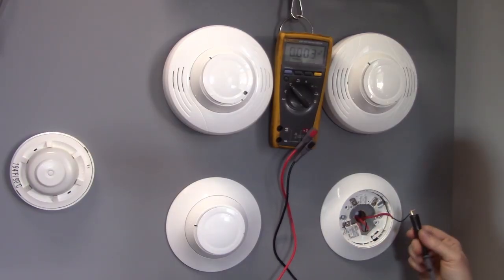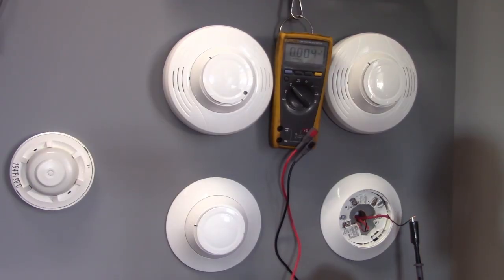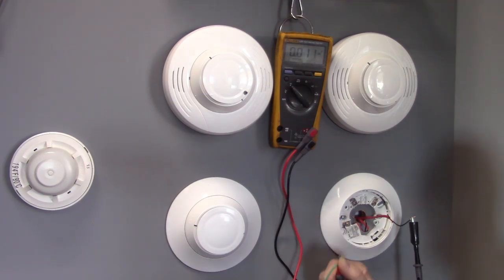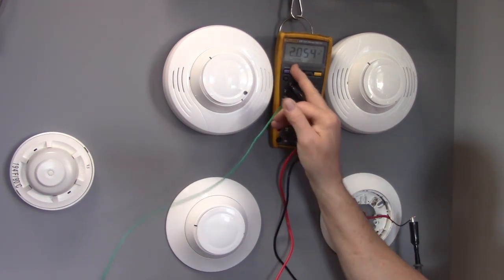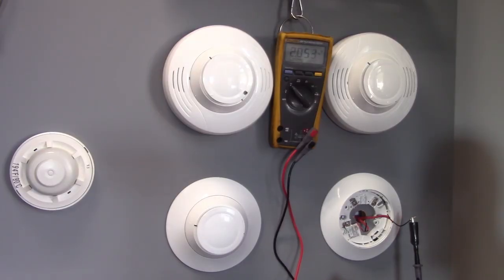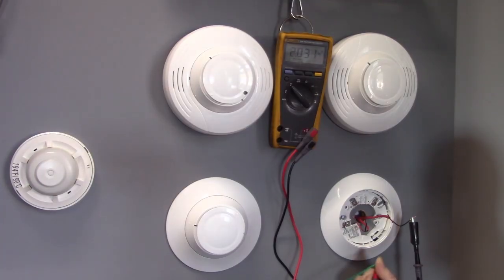This one has our SLC voltage. So this goes towards the fire panel. So now I've got a lead on negative. I'll put a lead on earth ground. There's my pulsing two volts, which is the normal state of the fire panel. So we know that the ground fault is further from this point.